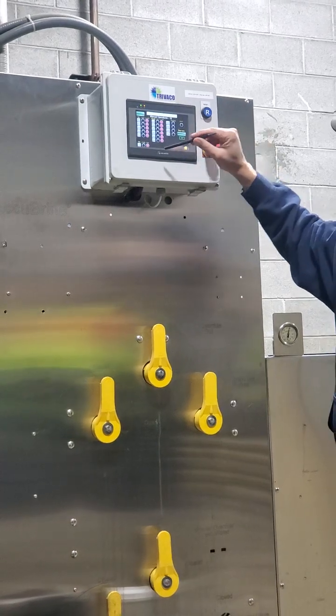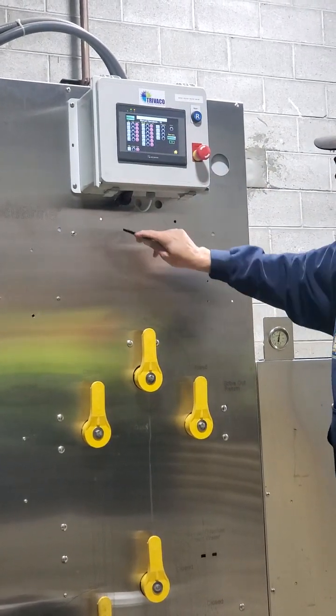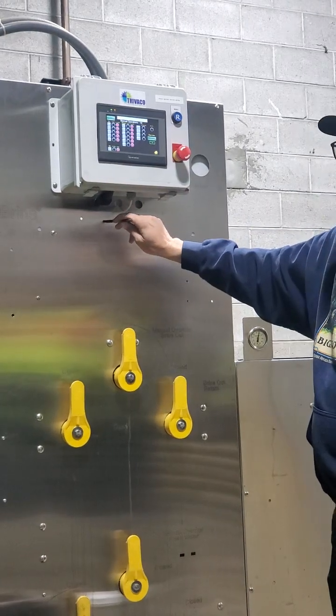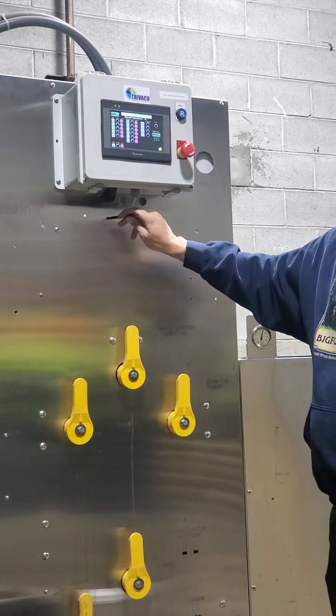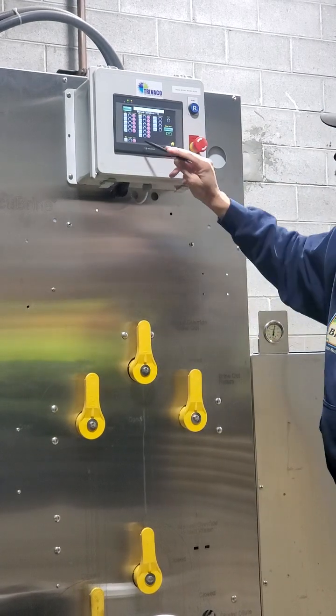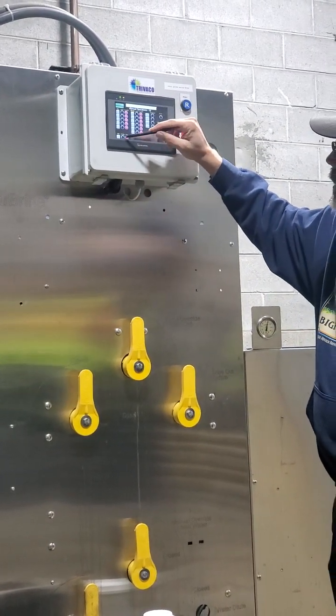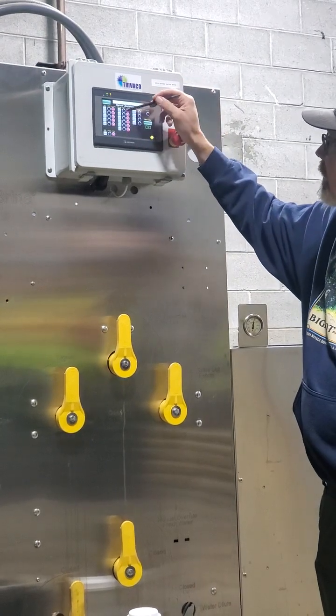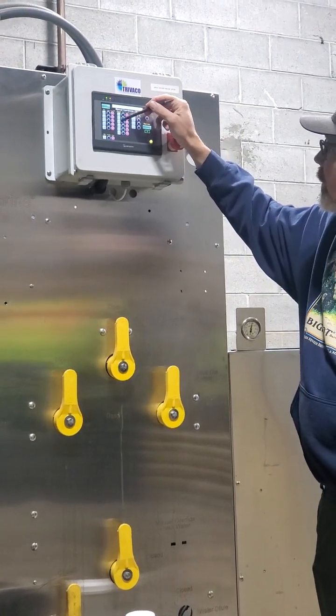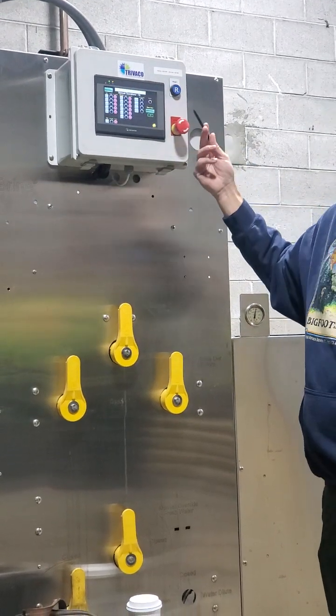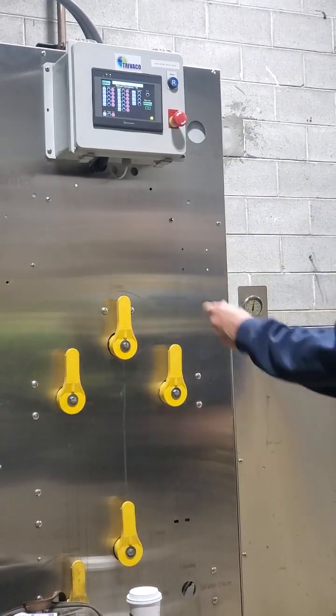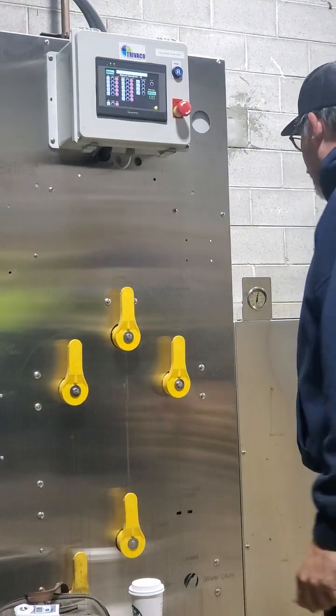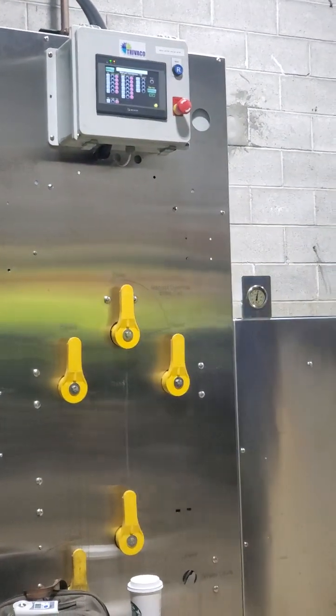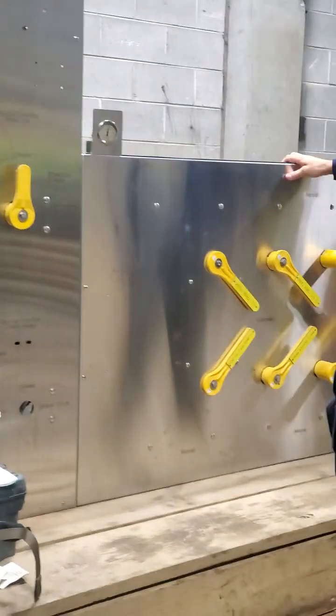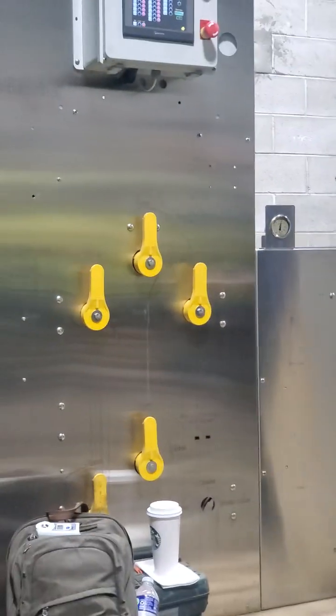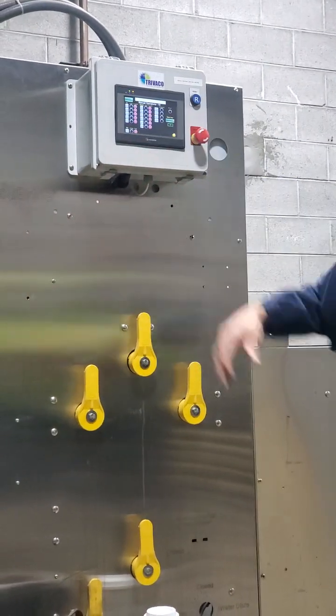That's the key, because this valve right here directs flow either to the salt tank or the storage tank. If you do it here, during the brine making process, it's going from salt to brine, and that's what it'll look like. But if you change this to panel, you're just telling the valve that you're sending liquid to the panel over here, and now it's up to you to choose what it's pulling from and where it's going.